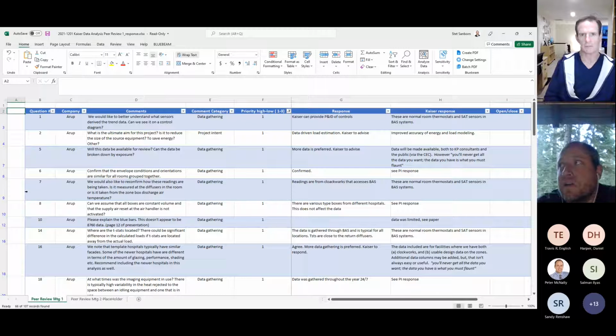One conversation we haven't fully had is that as we look at these opportunities to downsize, our own outside air temperature measurements were showing we were often far exceeding the design day, even the conservative design day. The most extreme was at our site that's supposed to be in a marine climate, but if any of you are in the Bay Area, you know we've had a bunch of heat waves in the last year that exceeded it. So what's the relationship between right-sizing upstream systems while also preparing for design days far in excess of what ASHRAE might be prescribing?